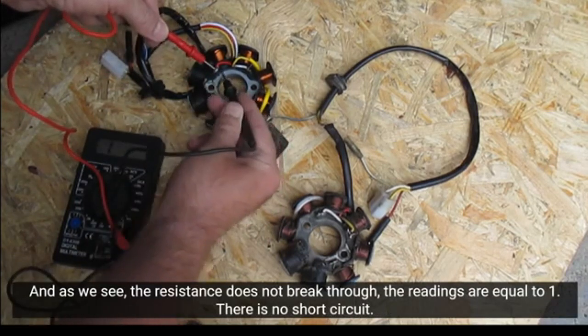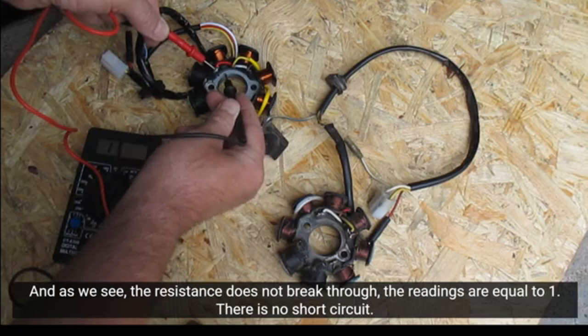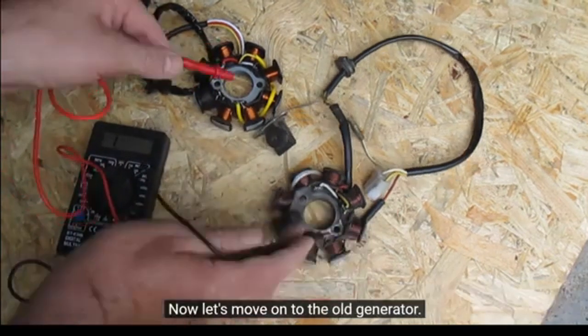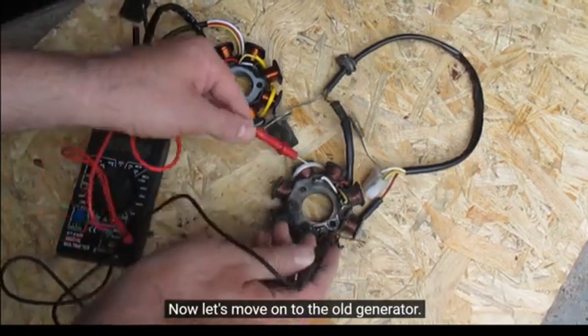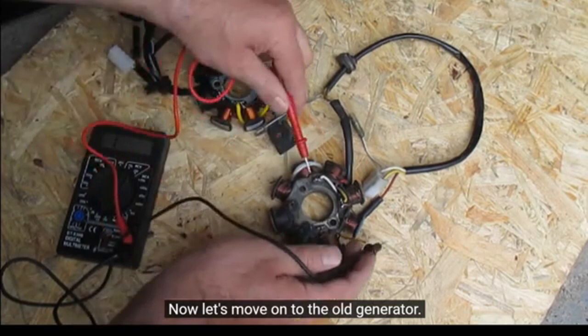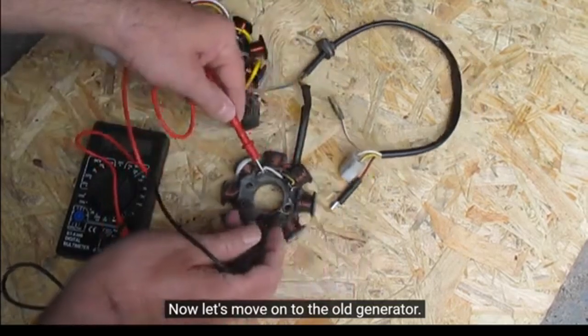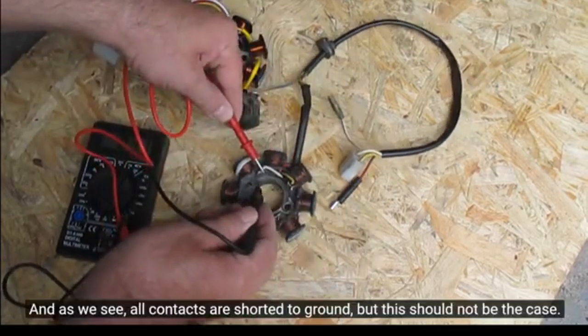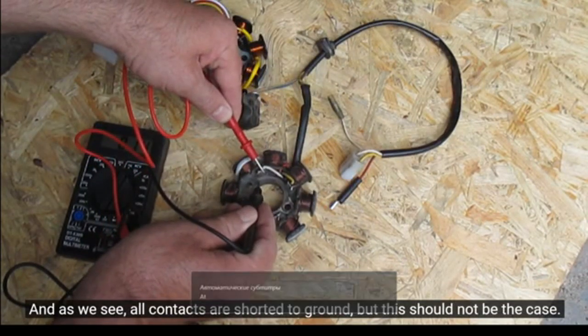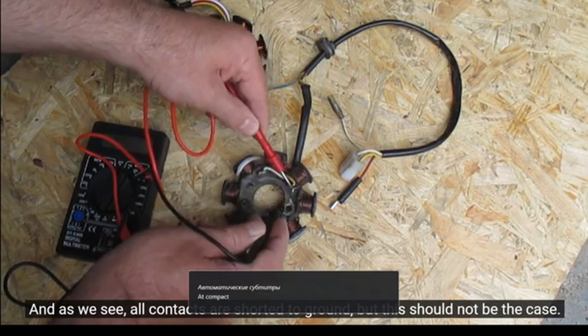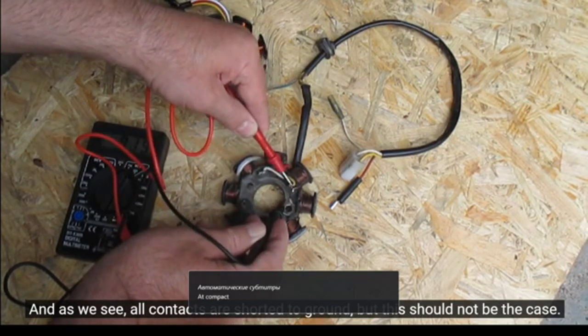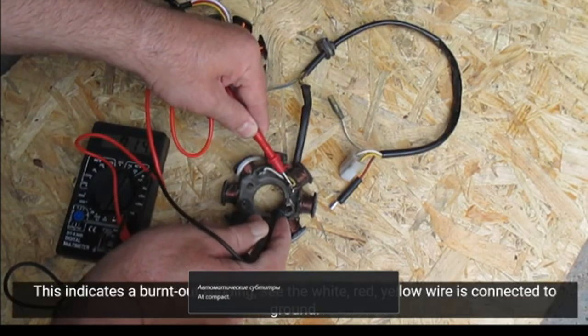I purchased a new generator and want to show the difference between the new and old generator. I set the multimeter lever to a resistance of 2000 ohms. I put one end of the probe on ground, the other on all contacts. And as we see, the resistance does not break through. The readings are equal to 1. There is no short circuit.